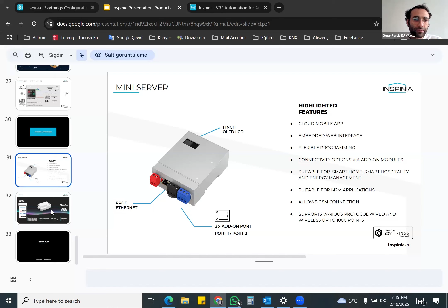The VRV add-on solution is completely an outdoor unit solution. This is a very critical point. So for add-ons, when we're talking about add-ons for HVAC for a VRV system, we connect to the outdoor unit directly, using the central management port. But for AirCon, this is for indoor units, and each indoor unit needs one AirCon interface. For this solution, compatibility is very critical, so you need to check compatibility with representatives or with a checker tool for this AirCon interface.